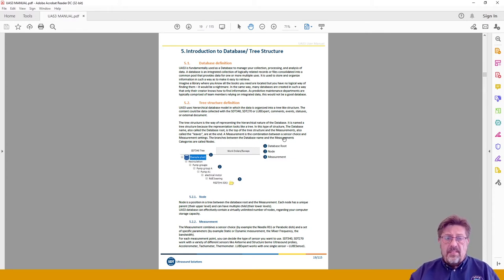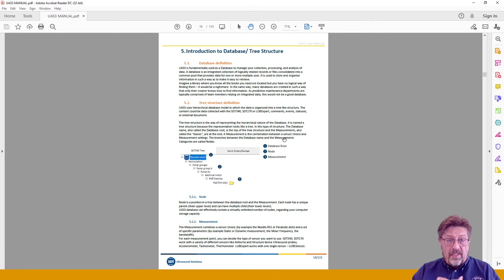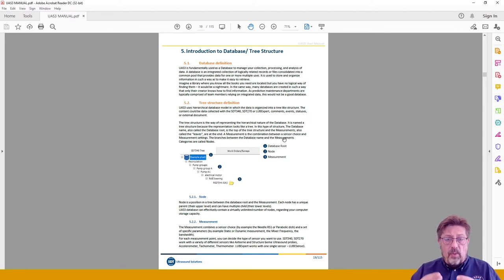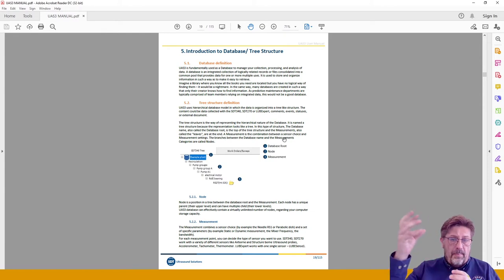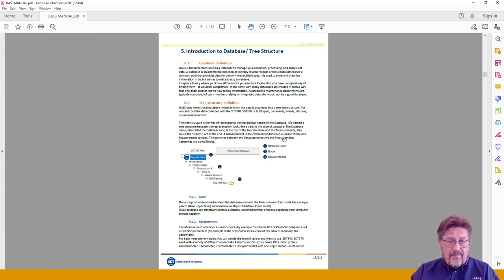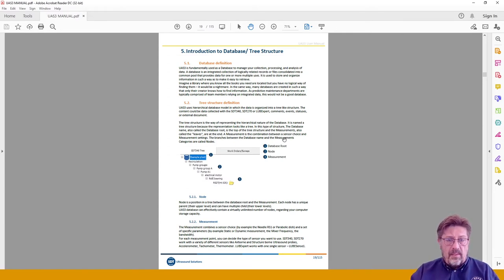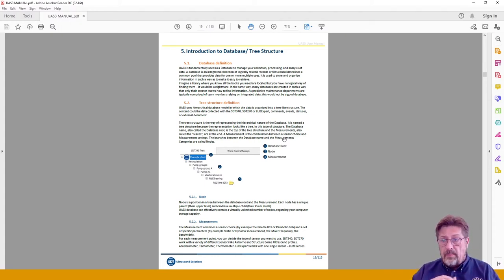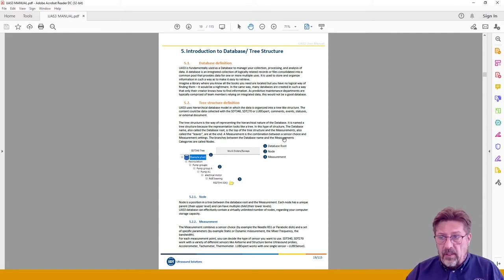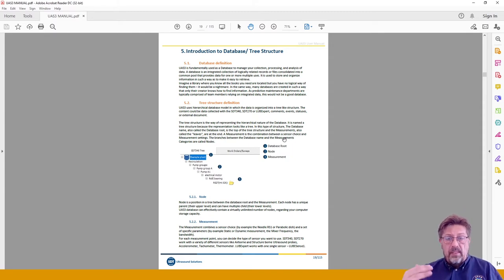The tree structure is divided into nodes. Just like any tree, the top name is called the database root. From the root you will have branches — these are called tree nodes — and it all ends with a measurement, which you can visualize as a leaf. From the database root you can use six levels of nodes, and the seventh must be the measurement setting. For example: a circulation unit, then pump groups, then pump group A, then pump one, then an electrical motor, then a non-drive end bearing, and then the measurement settings are built at that level.